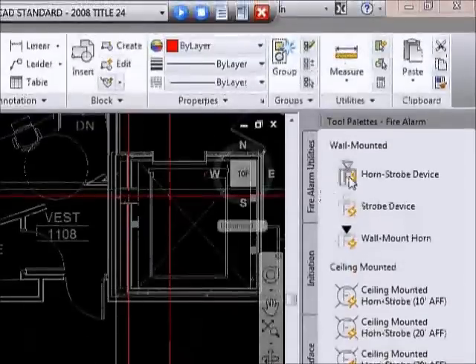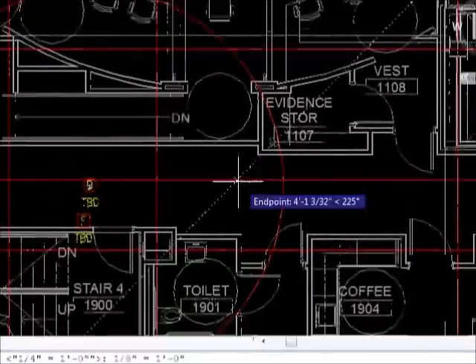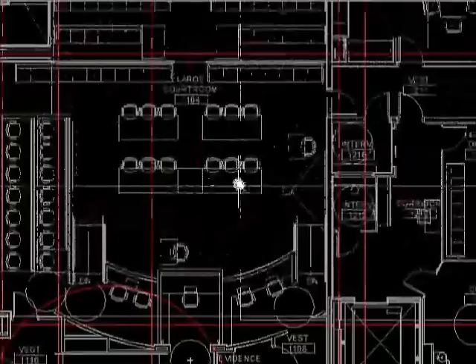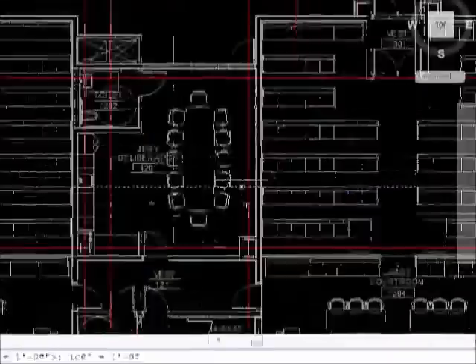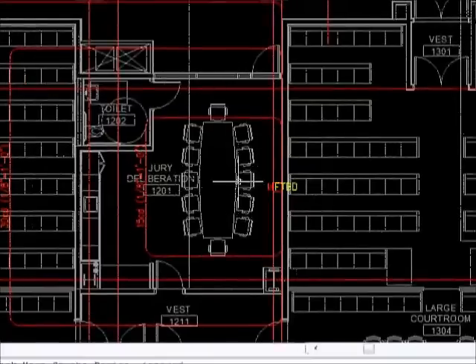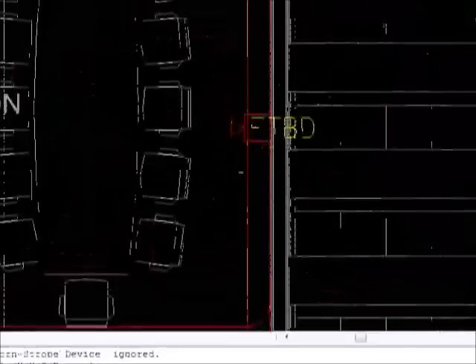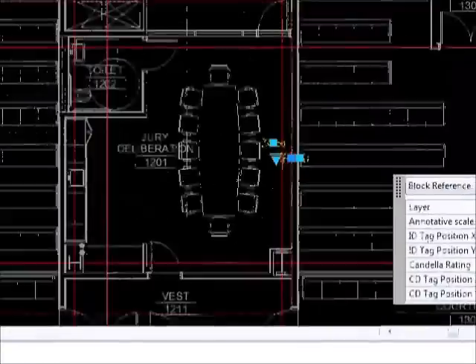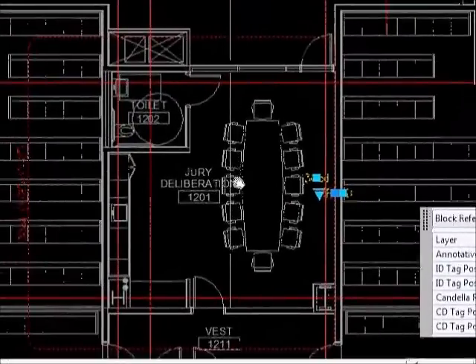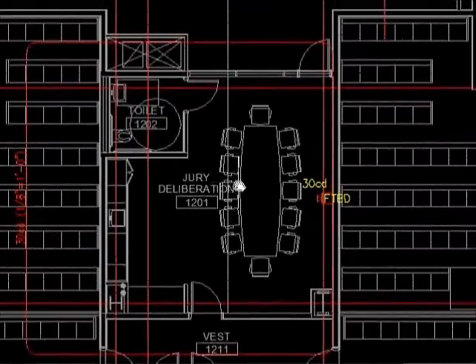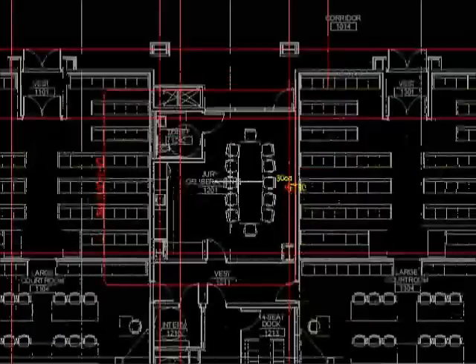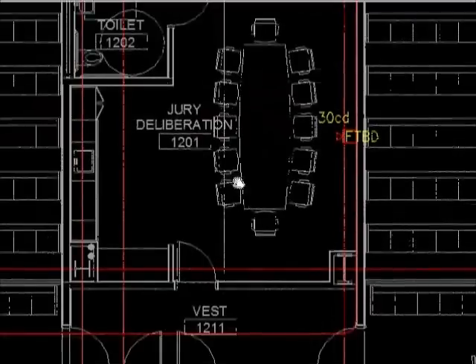Now the notification devices also have templates, so we can place a device. For example, if I were to place a device in this room, then I can look at it and determine which candela I need. Go over here and select that. Drop down and go to 30 CD and the template stays on. This is helpful in being able to do layouts where you have overlapping devices that have overlapping coverage.